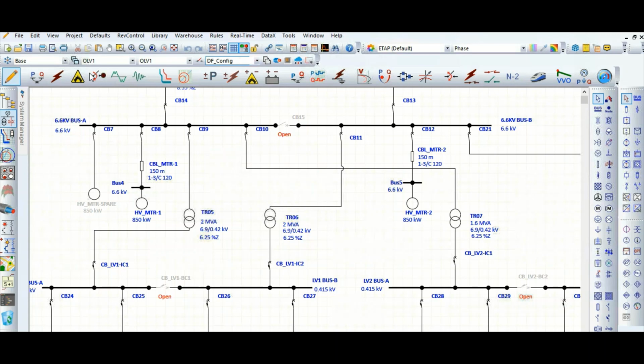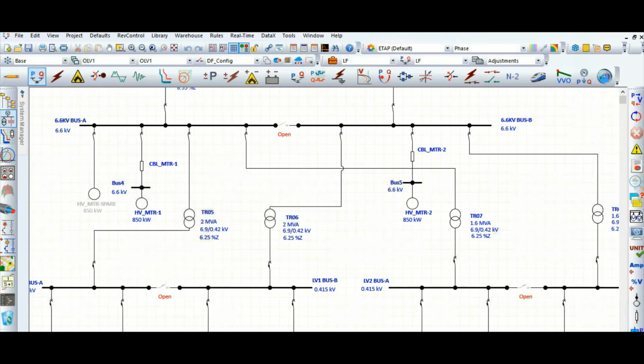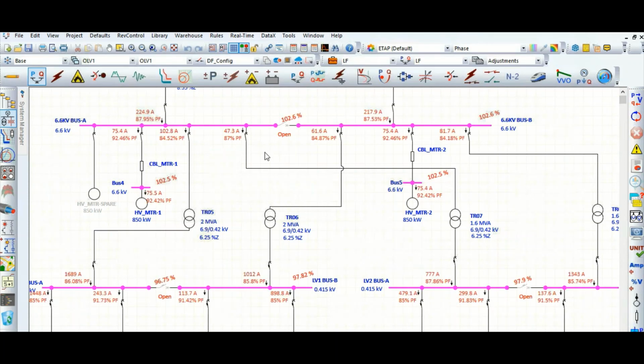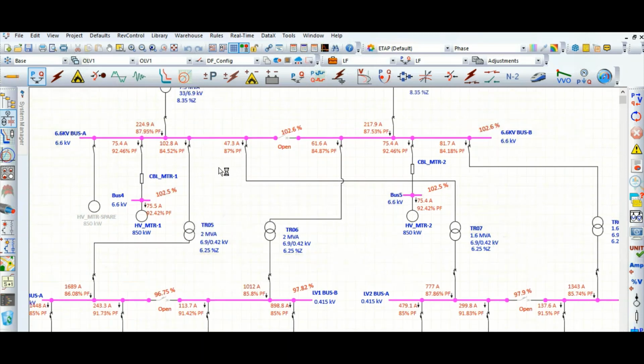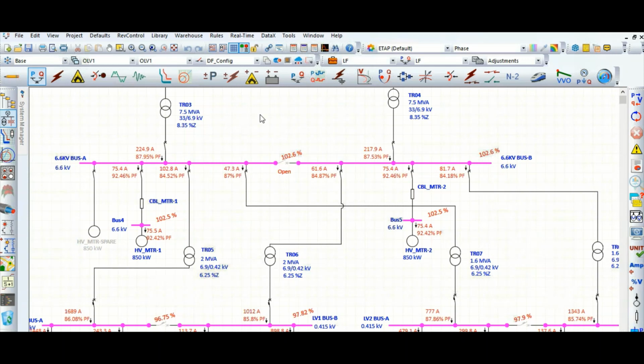To improve the voltage profile, let's run the load flow first. In the dual feeder configuration, where two incomers are on and the bus coupler breaker is off, the bus voltage you can see is 102.6%, and here the under voltage is 96.75%, almost 97-98%. So how do we improve the bus voltages and sort out the under voltage or over voltage issues in the bus? Using transformer tap changing, fixed tap positions.